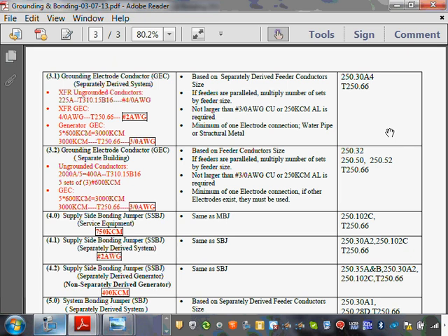Any comments, guys? Any questions? So that's my grounding electrode conductor coming out of the separately derived system transformer. That conductor can be directly tied to the steel of the building, can be tied to the water pipe, or can go all the way back to the ground bar in your building. Any comments, guys? Any questions?